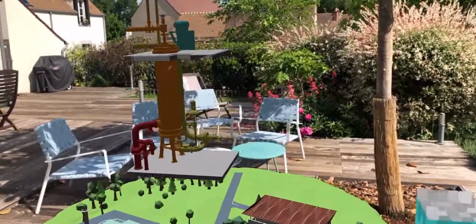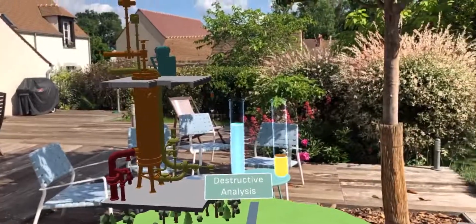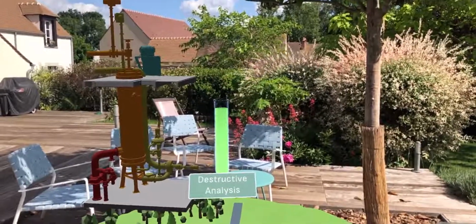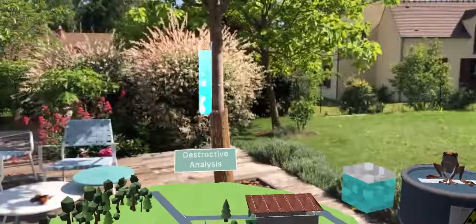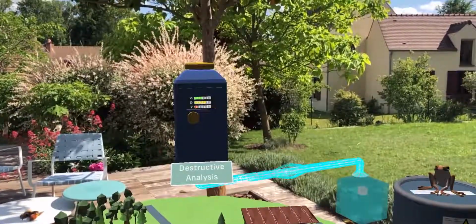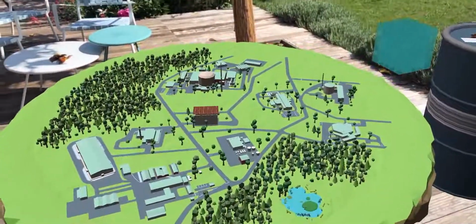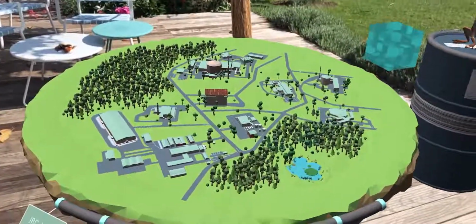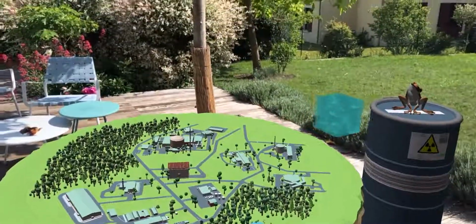Samples of the components are extracted and submitted for advanced radiological tests in the laboratories. All 3 types of radioactivity, alpha, beta and gamma, are measured, and the correlation between gamma and the other 2 types can be determined. Keep this in mind because this proportion between gamma and alpha, beta will be used later. Excellent. By this, the process of the plant characterization is finished. All the components are assigned to homogeneous groups and must not be mixed up subsequently, for the entire duration of the process. Let's move on to the second step.